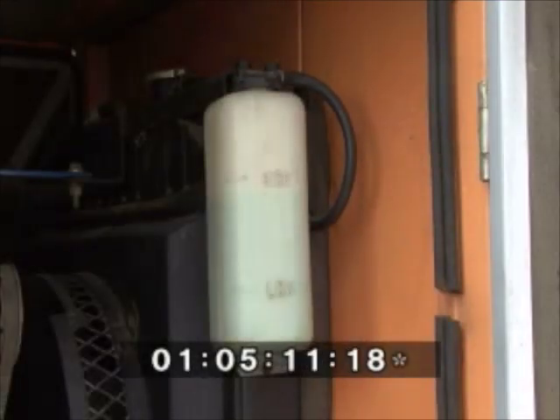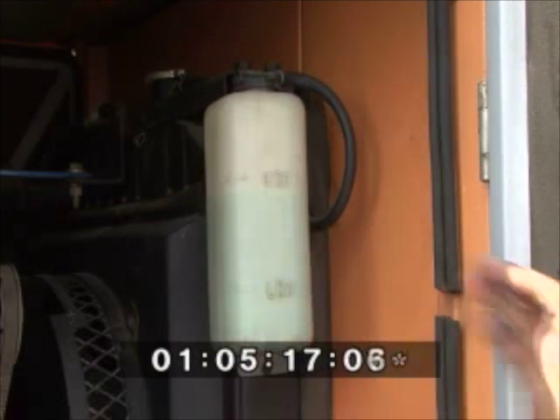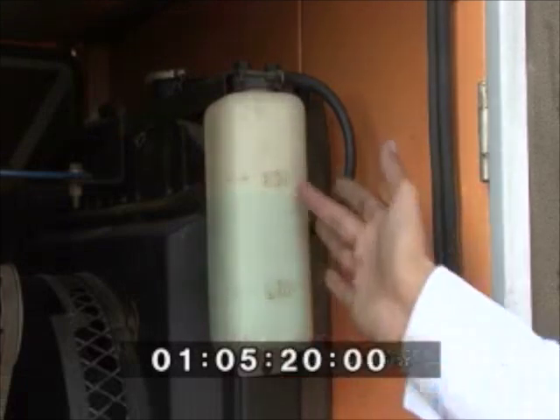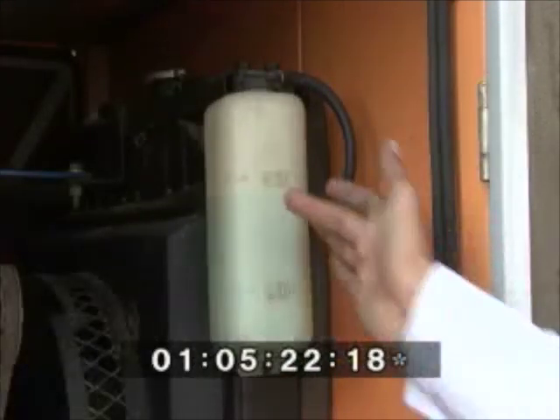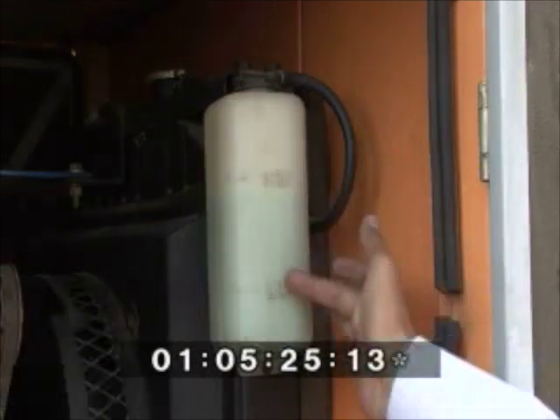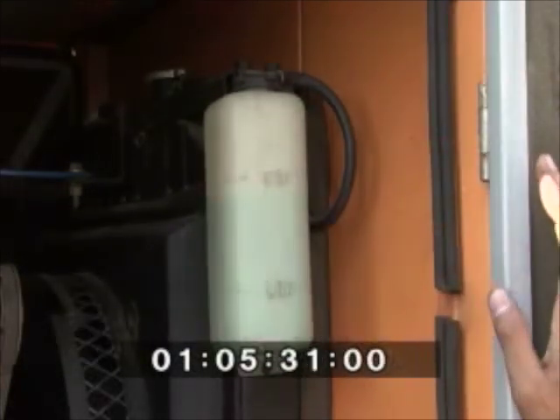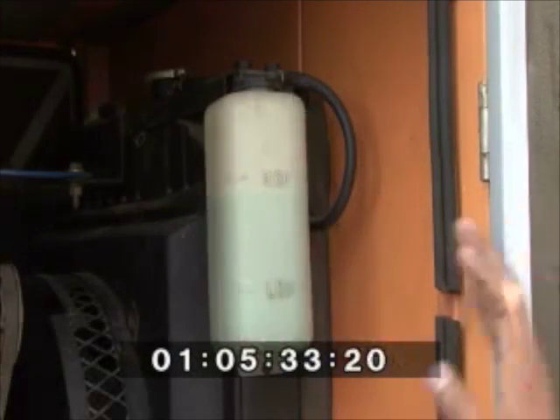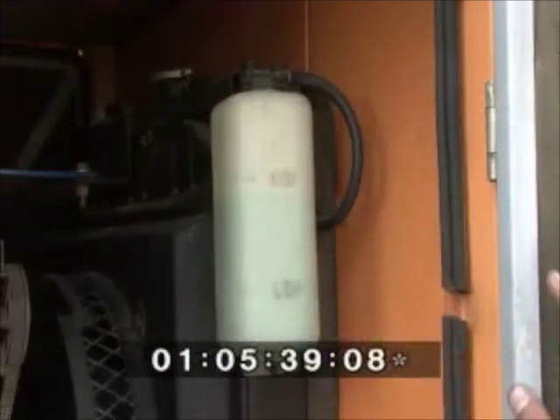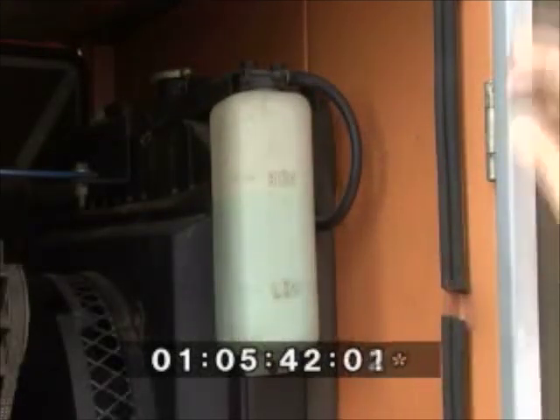Now we will see how to top up the DG coolant. You can now see the coolant bottle of the DG. The coolant avoids overheating of the DG while it is running. You can see two levels marked on it, high and low. The level of the coolant should be a little lower than the high mark on the bottle. In case the level of the coolant is lower than the desired level, then we need to top up.